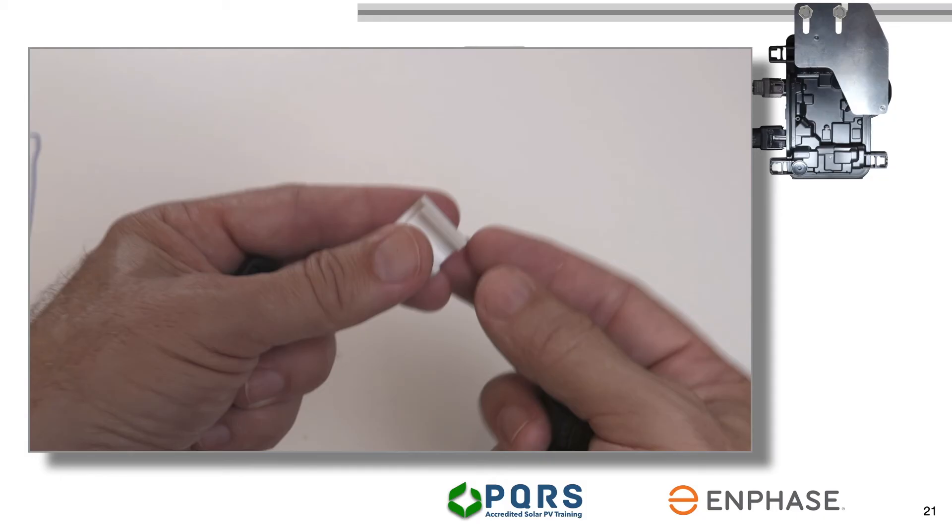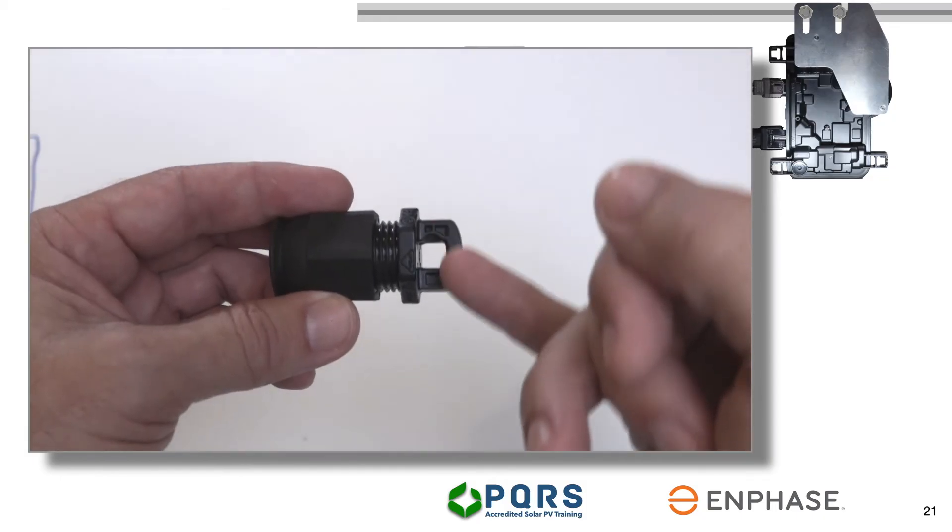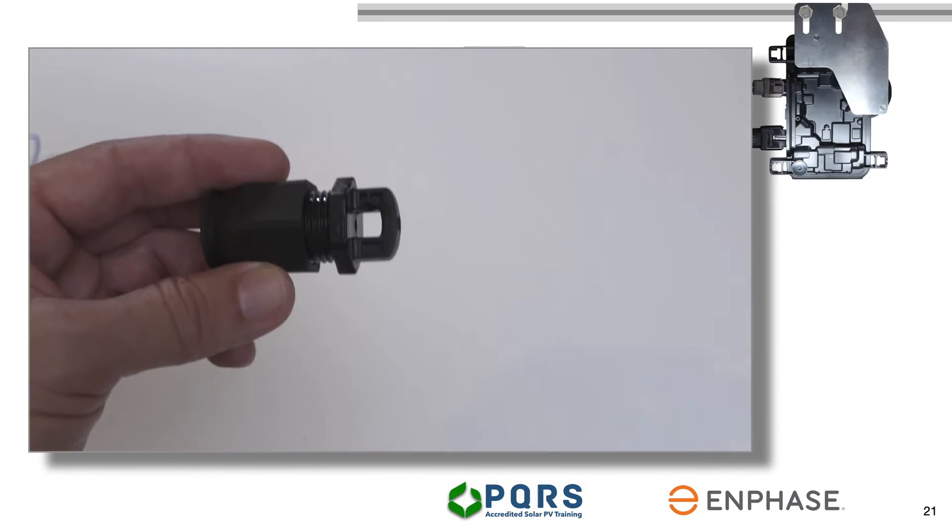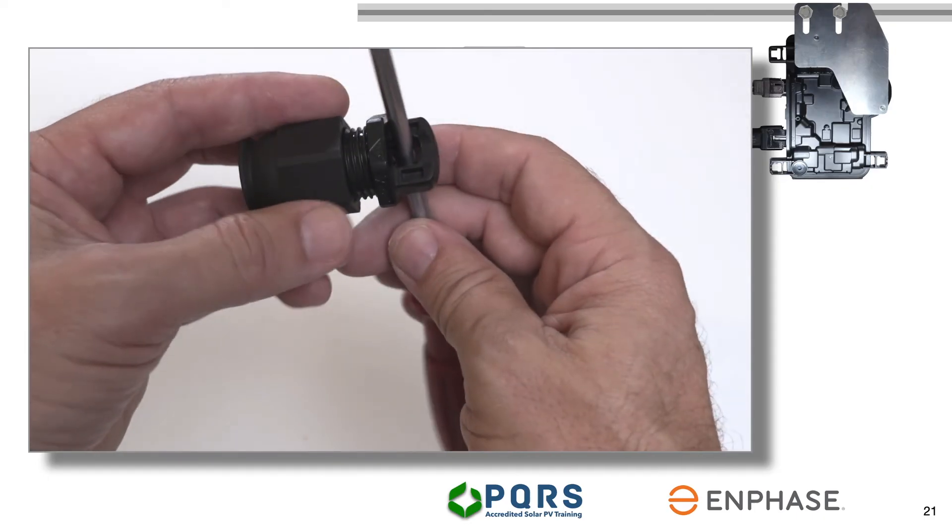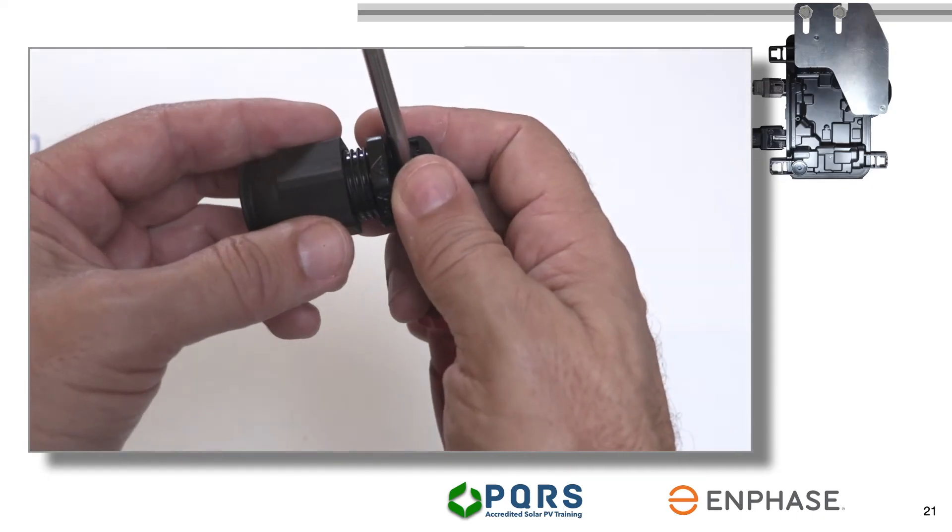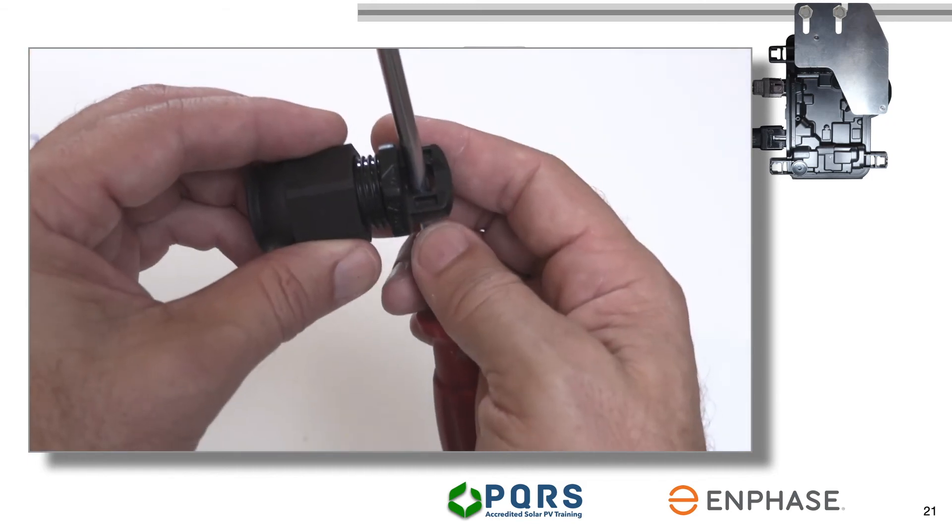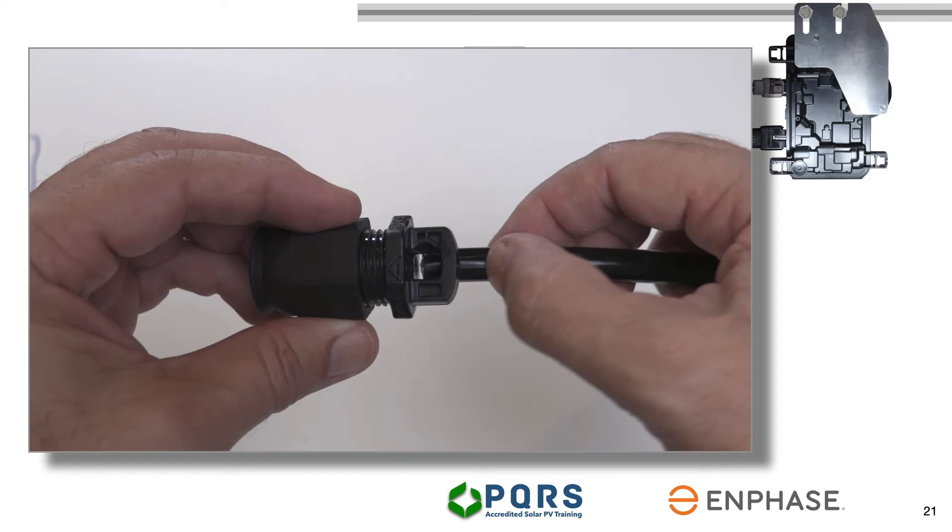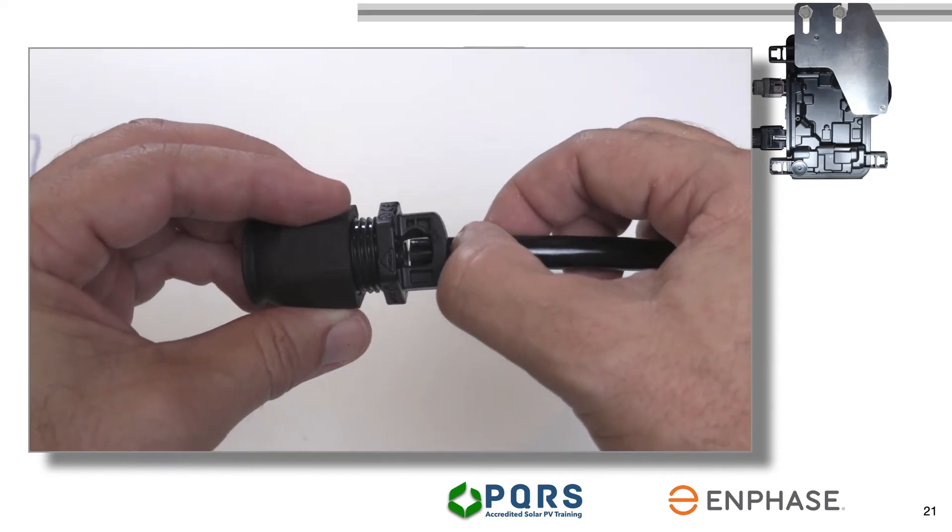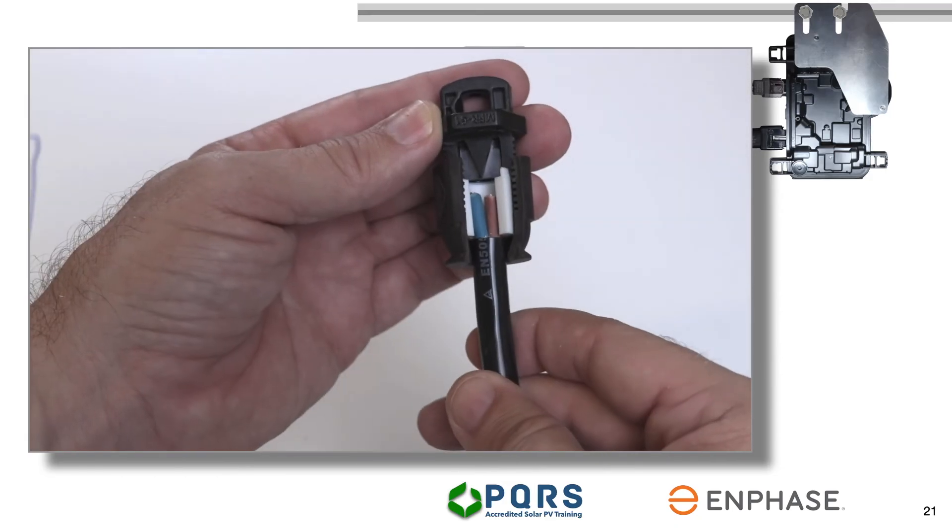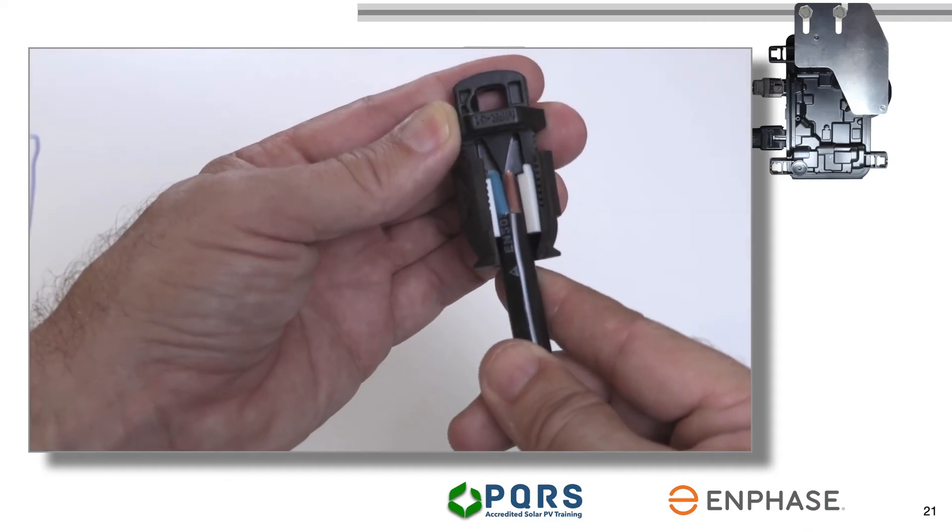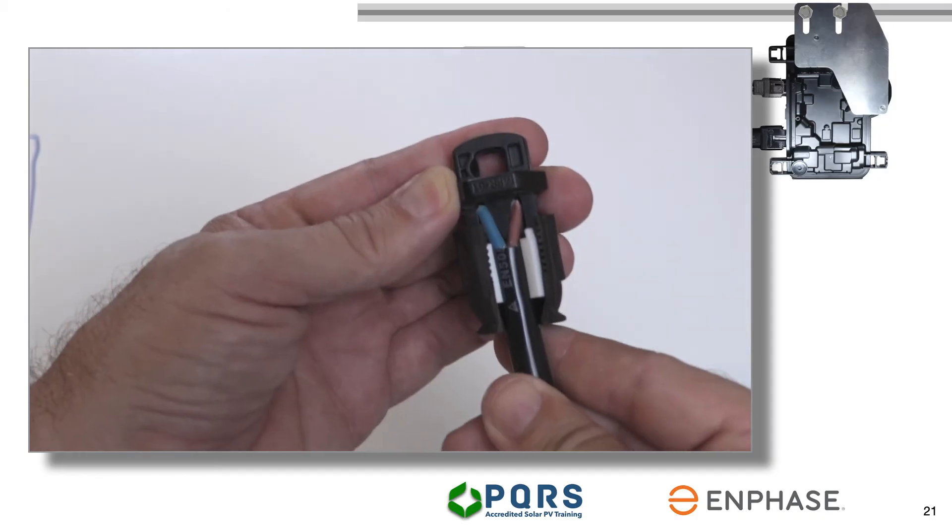A body, a grommet, and a nut. The back end of the Q-terminator is extended with a hole that can be used to keep the body in a fixed position with something like a screwdriver while fastening the nut with pliers or a spanner. It also serves as a guide that helps determine the exact amount of insulation that needs to be stripped back as we expose the two conductors that will be separated by the V-shape inside the terminator.